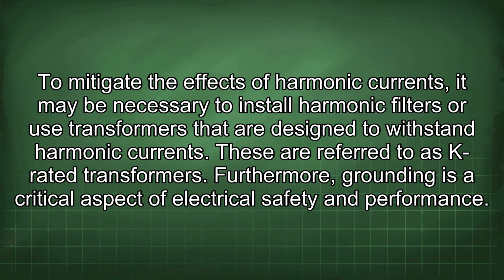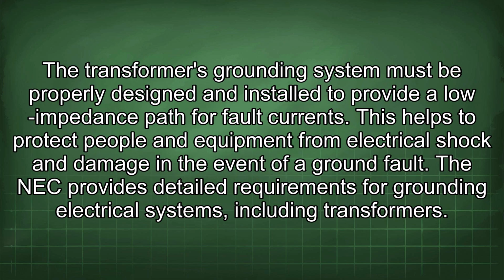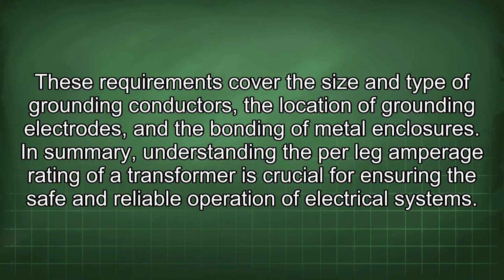Furthermore, grounding is a critical aspect of electrical safety and performance. The transformer's grounding system must be properly designed and installed to provide a low impedance path for fault currents. This helps to protect people and equipment from electrical shock and damage in the event of a ground fault. The NEC provides detailed requirements for grounding electrical systems, including transformers. These requirements cover the size and type of grounding conductors, the location of grounding electrodes, and the bonding of metal enclosures.